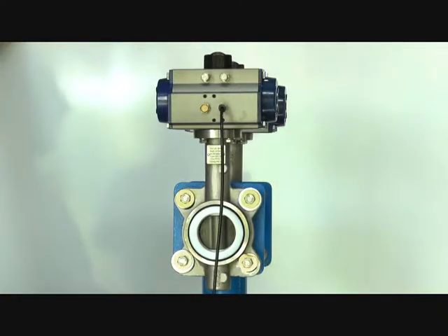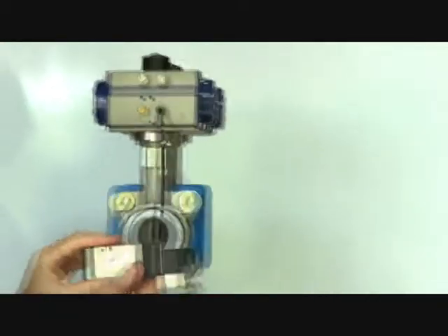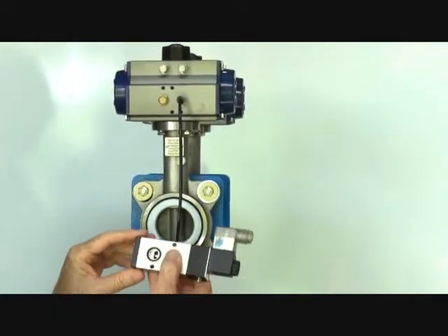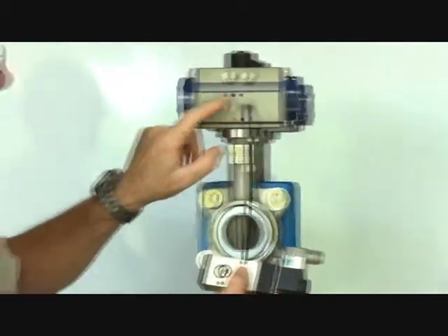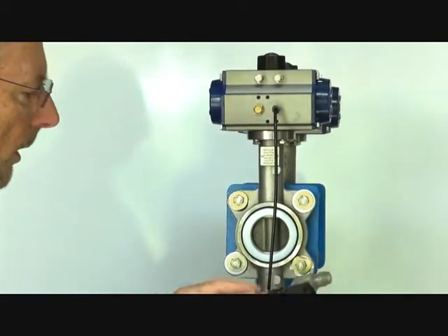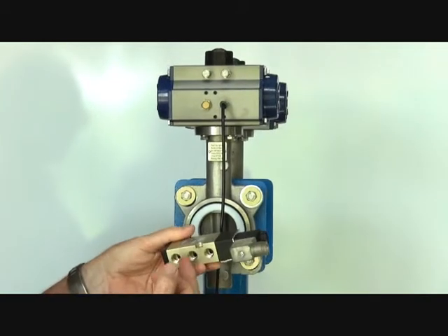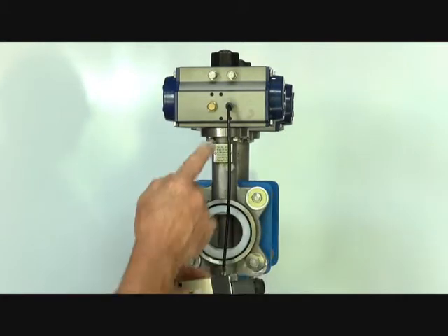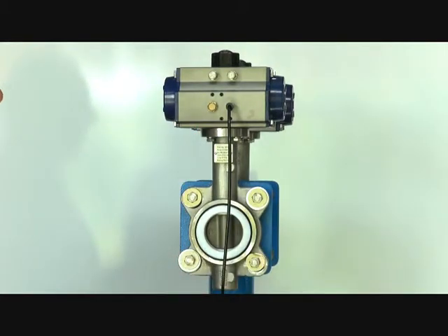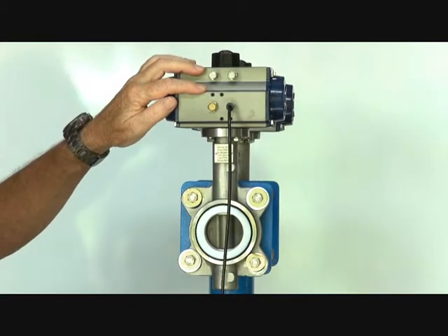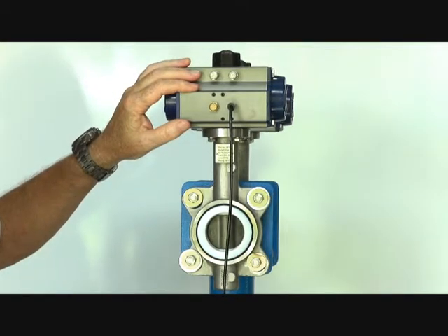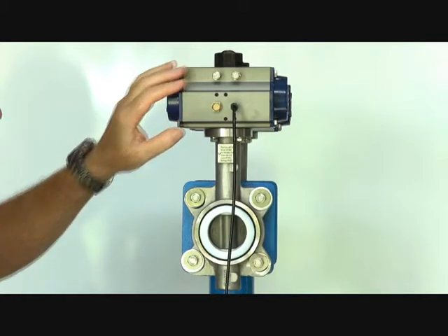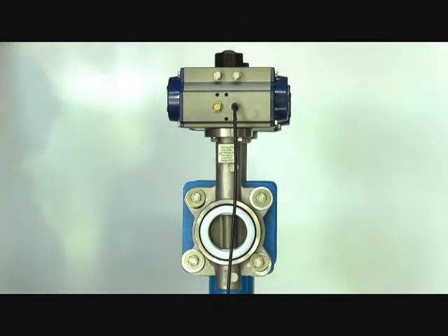We also recommend if you're going to use a solenoid valve to have a direct couple valve like this. This is a NAMUR interface, mounts directly onto the actuator. In this particular case we put air signal in, air supply in and it puts air onto both sides of the actuator. The actuator can act as a spring return but also can act with air and spring return and that way you get filtered clean air going to both sides of the actuator. And you still have your fail safe spring function.